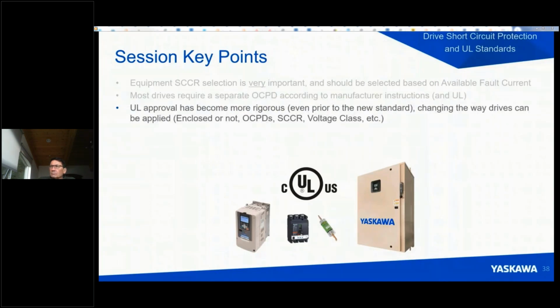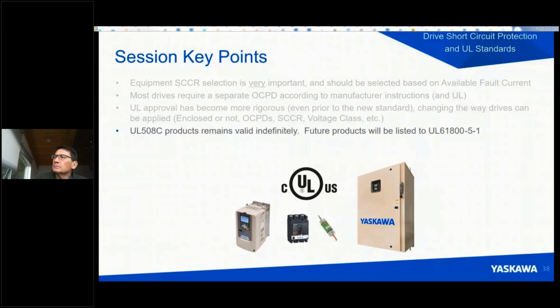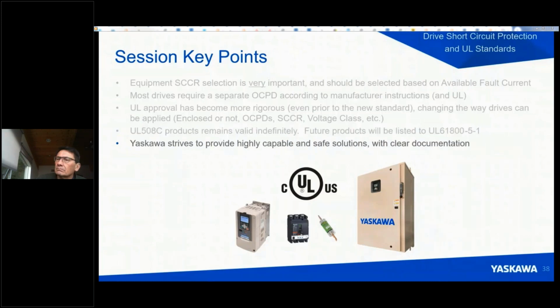Next, UL approval has become much more rigorous, even prior to the new standard, changing the way drives can be applied, such as enclosed or not, which protection device is chosen, what's required for short-circuit current rating, voltage class, etc. Again, UL approval has become much more rigorous. UL 508C products remain valid indefinitely, and future products will be listed to the new standard, which a lot of us are just referring to as 61800-5-1. And lastly, Yaskawa strives to provide highly reliable and safe solutions with very clear documentation.